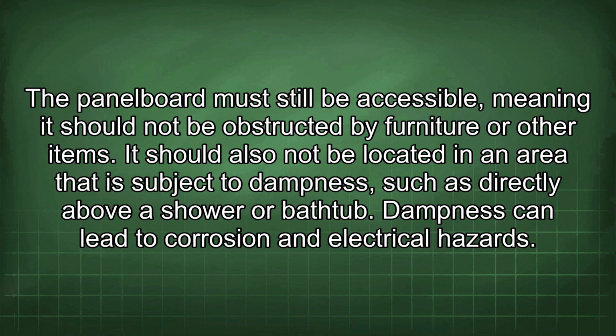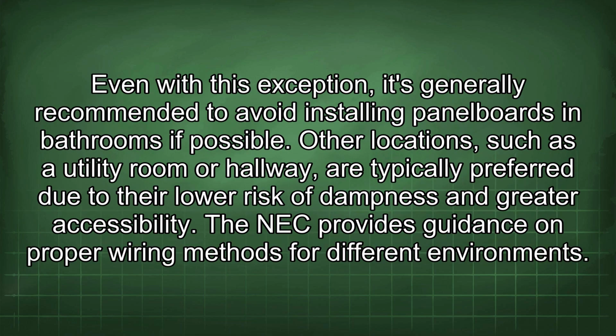It should also not be located in an area that is subject to dampness, such as directly above a shower or bathtub. Dampness can lead to corrosion and electrical hazards. Even with this exception, it's generally recommended to avoid installing panel boards in bathrooms if possible. Other locations, such as a utility room or hallway, are typically preferred due to their low risk of dampness and greater accessibility.